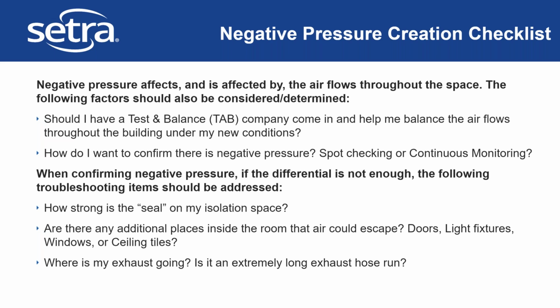I mentioned the Setra Lite, and we have a few different iterations of it. Whether you're setting up continuous monitoring or spot checking, it's important to think through how you can confirm that the negative pressure is actually working. You can set it up and think you're all good, but without some measurement—continuous or spot checking—it would be difficult to know if you've achieved that.